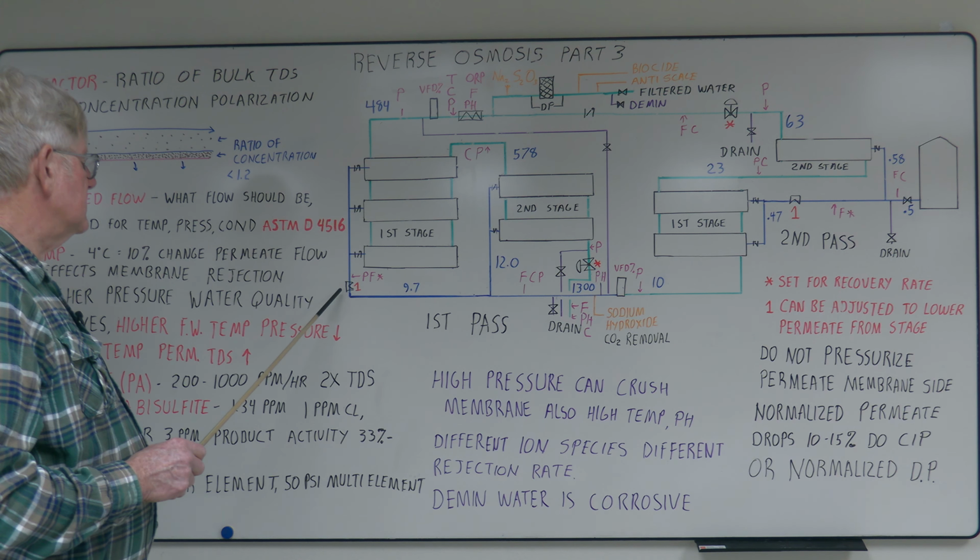Here you go to the second stage. Mention that. The big thing is your back pressure control valve. This is set. This determines how much back pressure is on this concentrate side, which determines the recovery, and then also how much permeate you have and how concentrated the wastewater becomes. Your permeate, you can add sodium hydroxide here if you want to get rid of carbon dioxide. The stage is further down. Gases are not taken out with an RO.